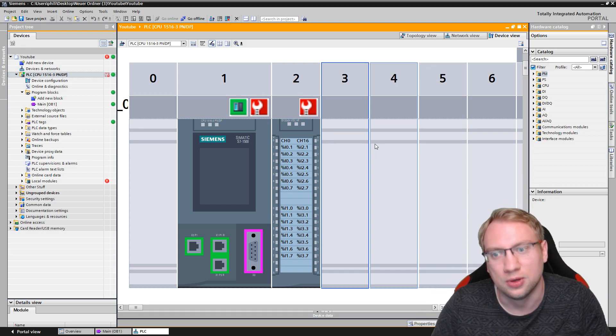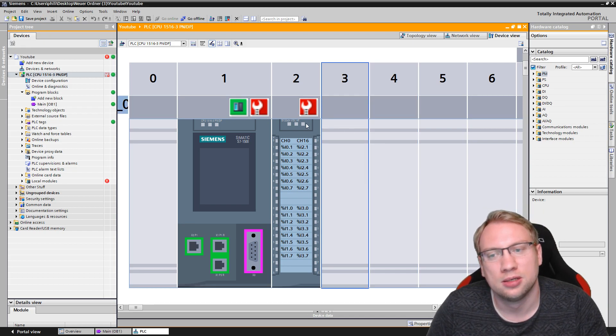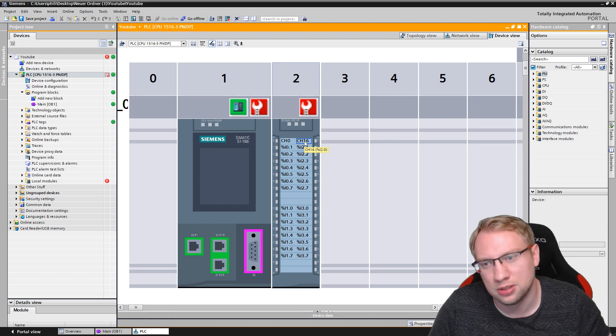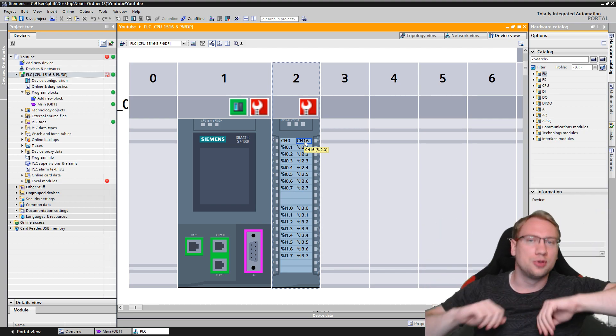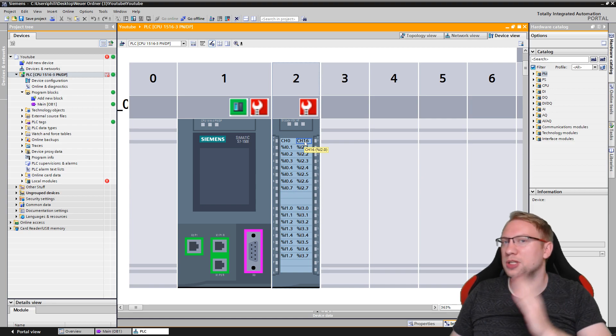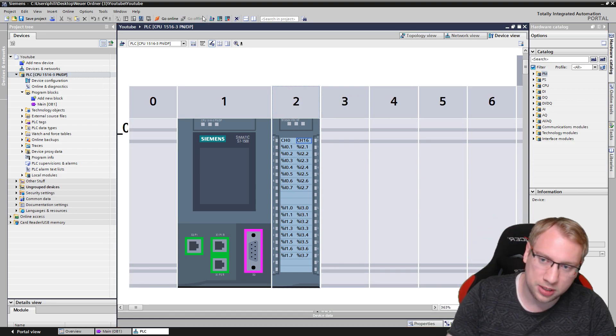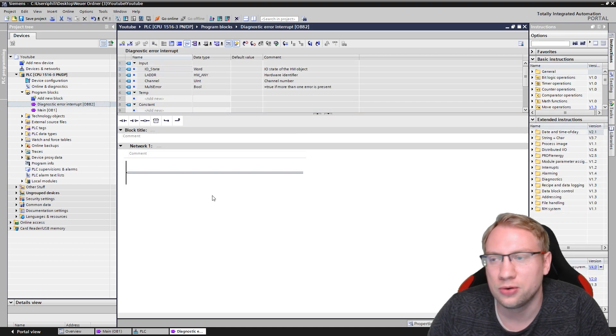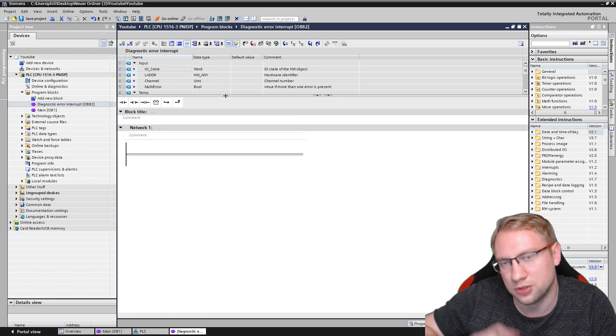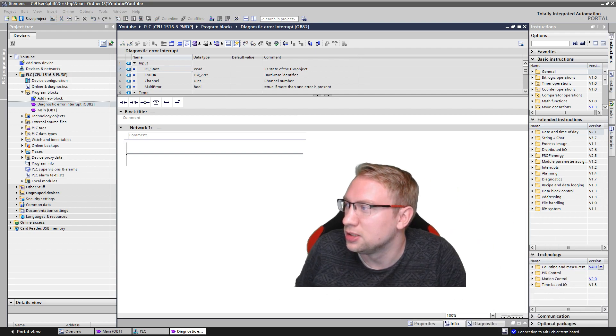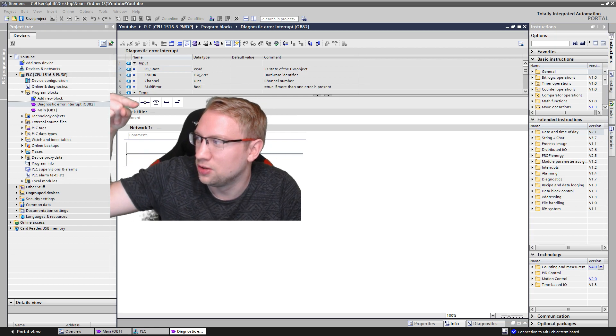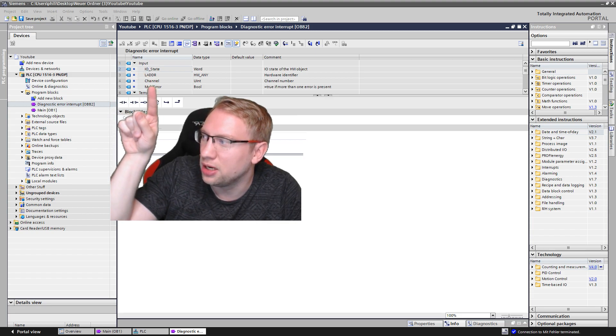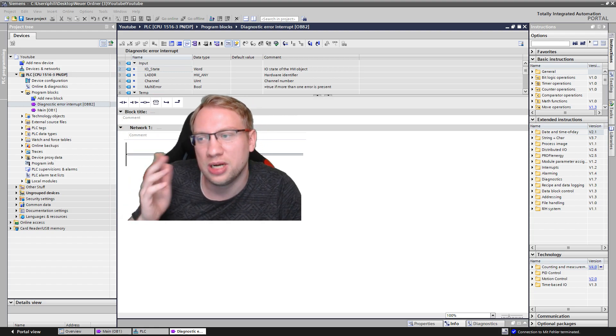This was all explained in the last video. What we are talking about here is how do we deal with this in OB82 — because how should my program react? How do I know if channel zero has the problem or channel 16? I need to distinguish which one has the problem, because we could have a thousand input modules and one of them has a problem. So I'll go offline, add a new block — the diagnostics error interrupt OB82. In this organization block there are special block parameters at the top.